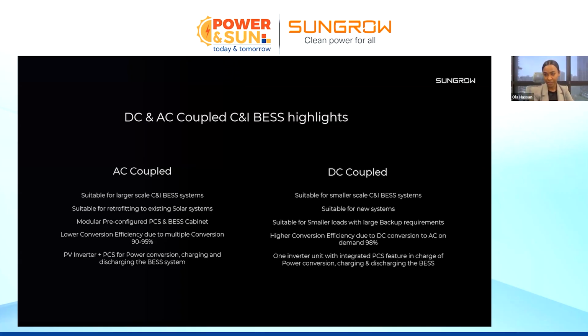Higher conversion efficiency, approximately 98%, due to the conversion from the DC side to AC. It's higher than the AC coupled. Why is that? Because the energy conversion over here is happening only one time. So when I have requirements or demand, then my inverter will discharge from the battery, convert to AC, and immediately inject it to my point of connection. Unlike the AC coupled, where a PV inverter converts from DC to AC, pushing it to the battery. Then again the PCS is converting from AC to DC, charging the batteries, storing the energy, and then again, when it's needed, it's converted to AC and then fed to the load.